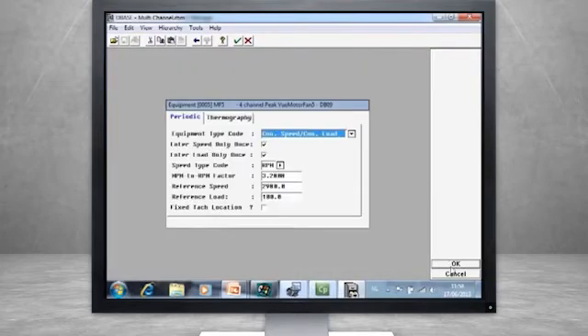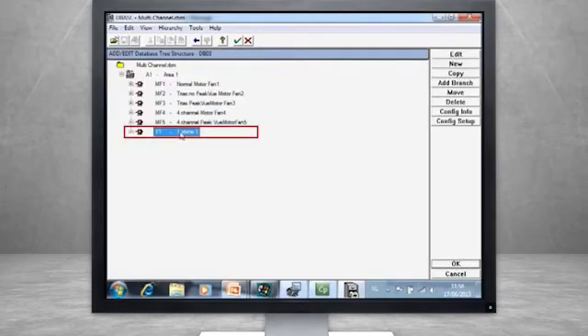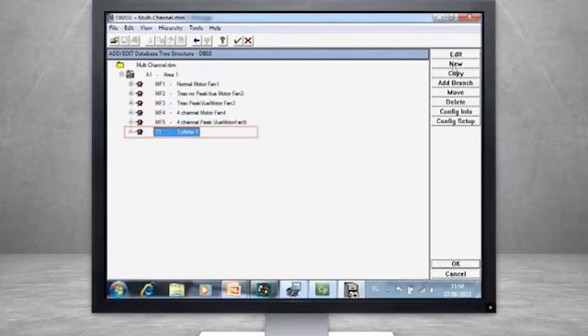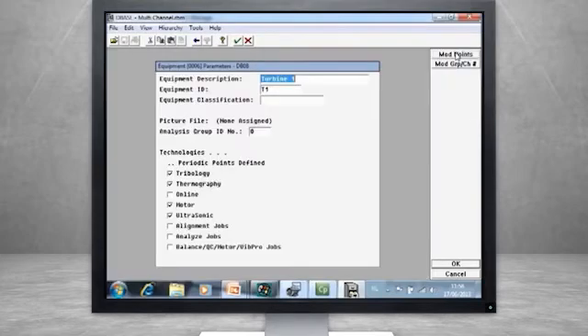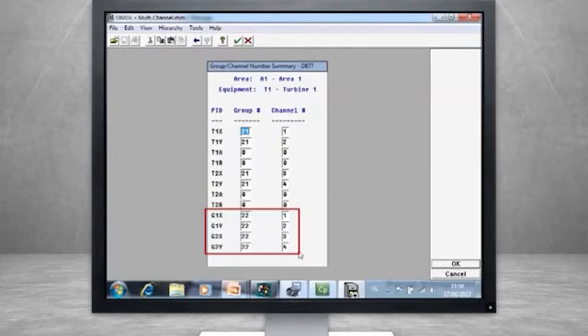The configurations we have reviewed were for rolling element bearings. Let's look at an example for a sleeve bearing. For the generator, we are using displacement probes. We can put them in the same group and assign them channels 1 through 4.